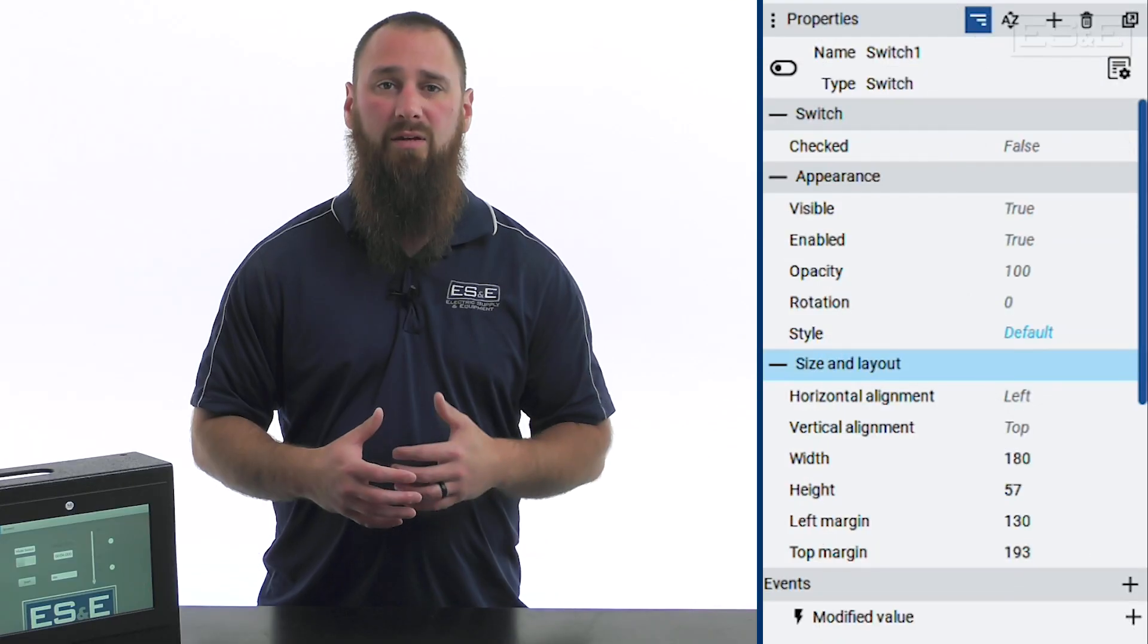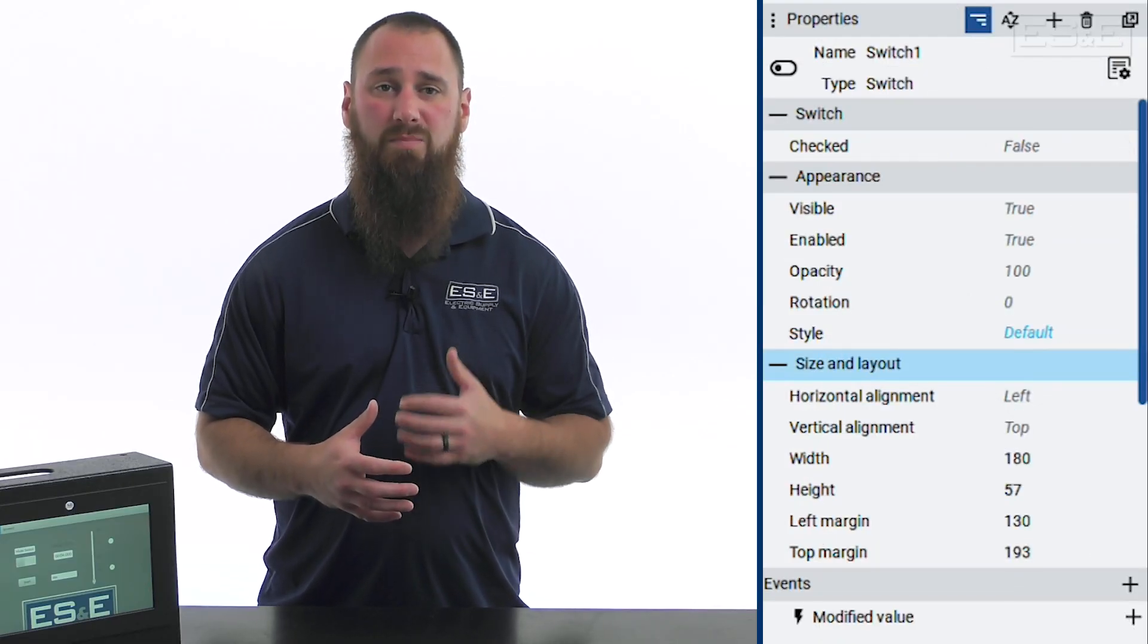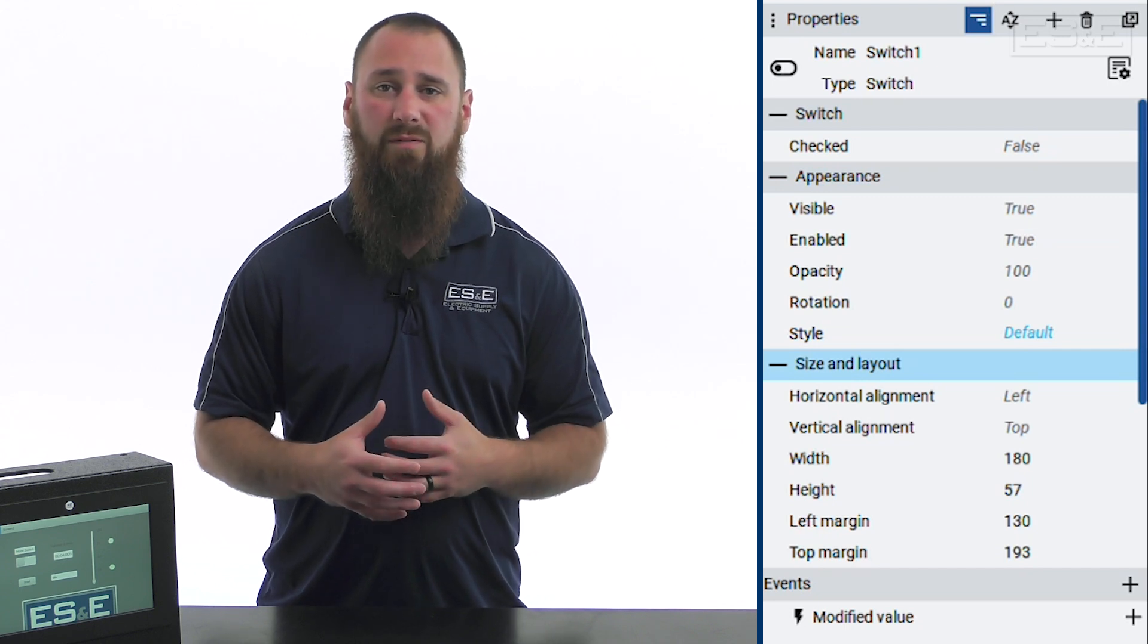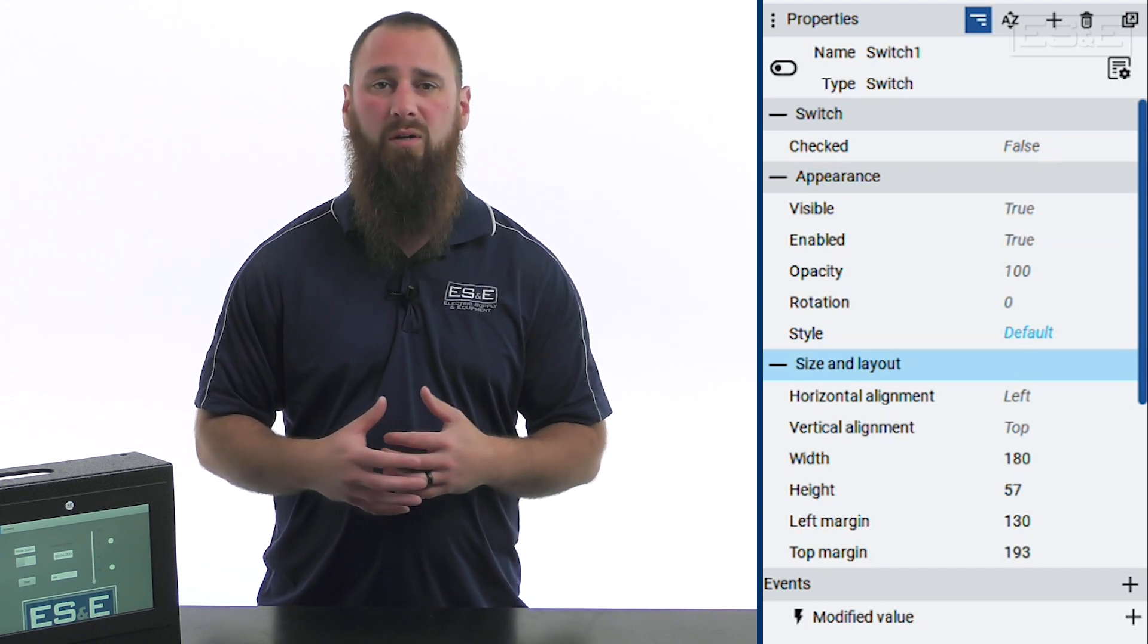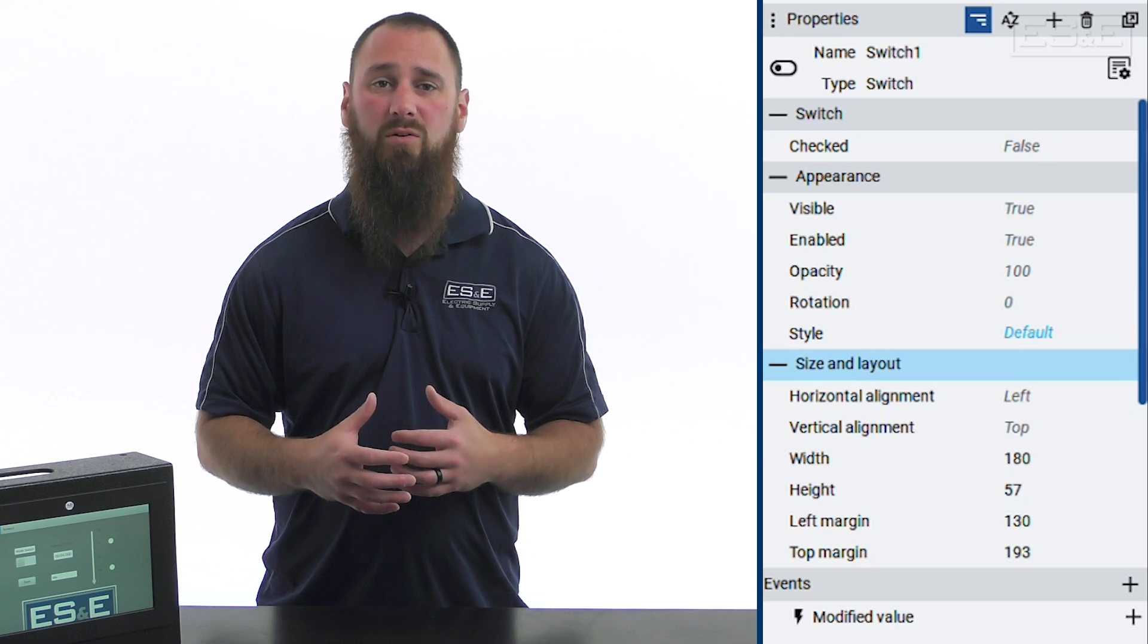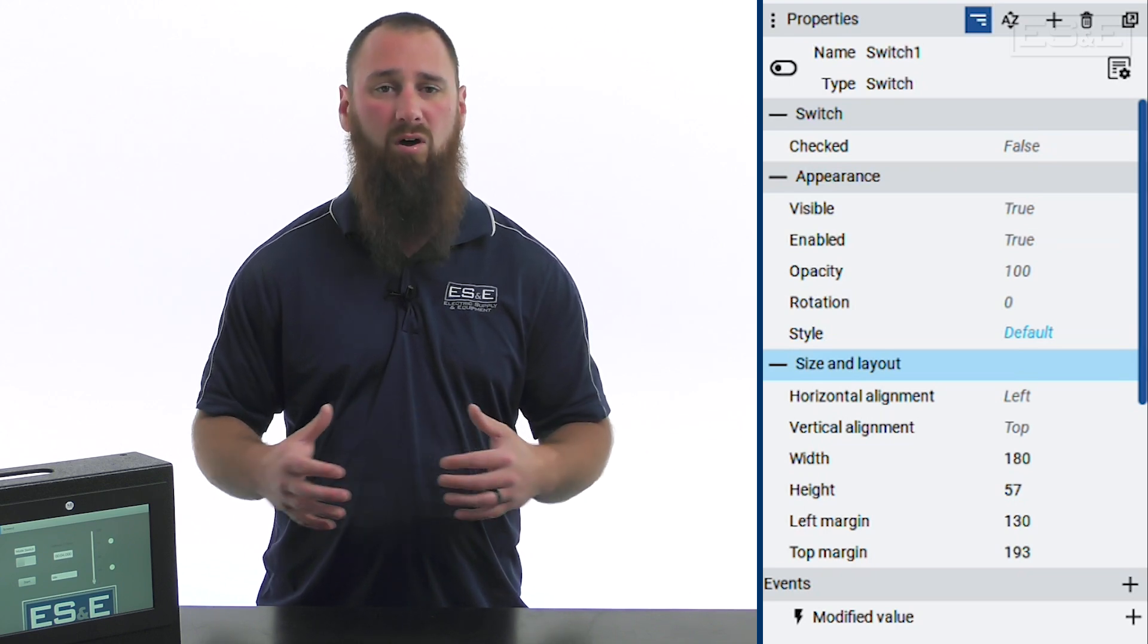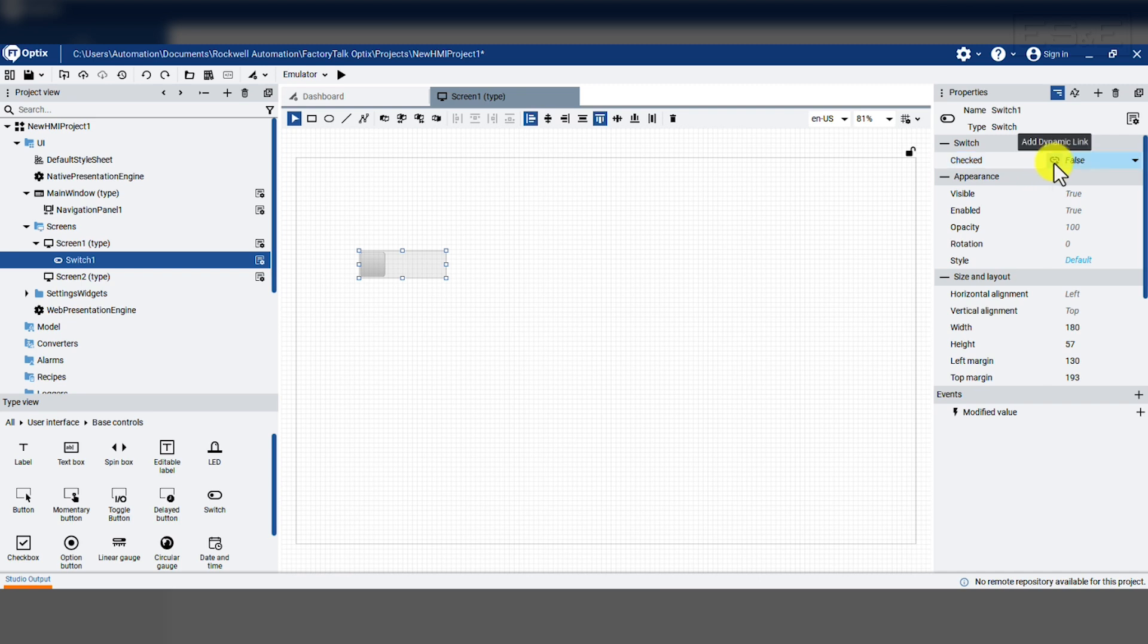Now that the switch is added, we need to tell it what is being done with the switch. That configuration is done in the property window. We will select the object and make sure that the property window is wide enough to see all the properties. We need to add a dynamic link for the property called checked, which is near the top of the property window.